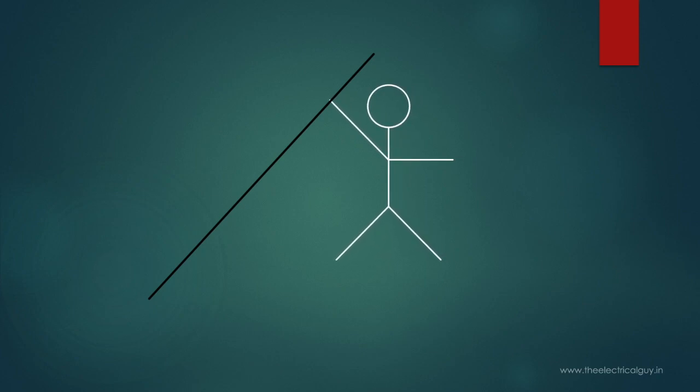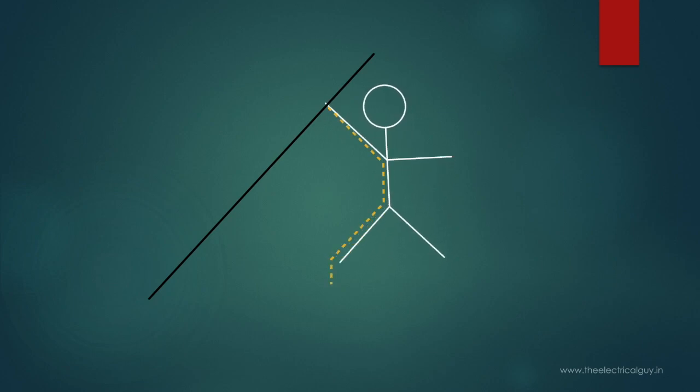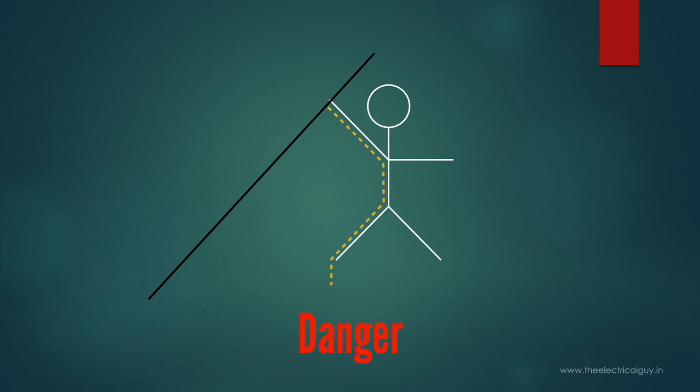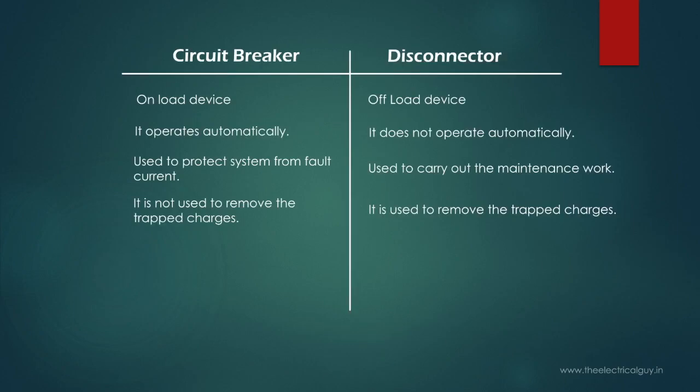there is a possibility that those trapped charges will flow through his body to ground. And in such case the life of that person is in danger. And hence to avoid such situations, disconnectors are provided with earth switches. After you open the disconnector, just close the earth switch and all the trapped charges will flow through that earth switch to ground. And of course this facility is not provided in circuit breaker.